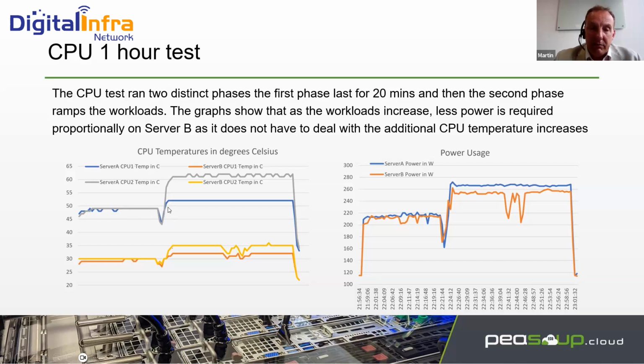What we do have is a much lower increase with liquid. We increased by about 5 degrees when stress testing the processor in liquid, whereas in air we increased by a good 10-plus degrees.